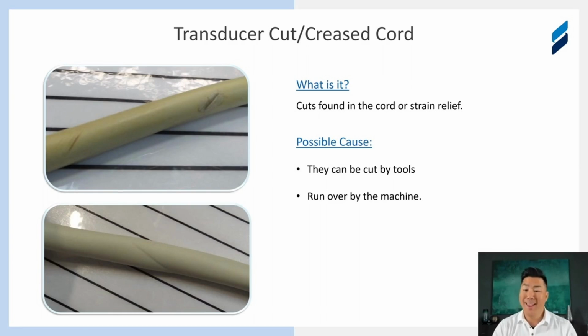noise could be coming from. And it's a great point to train and help educate sonographers to get the cables up off of the ground when you're moving a machine. When you roll them around, the cables do drag on the ground. Those wheels, these ultrasound machines weigh hundreds of pounds, and hundreds of pounds of machine against 42 gauge wires, the 42 gauge wires are going to lose every single time. So something here that could be nothing and could be superficial, but again, we have seen on many occasions that this is the source of a lot of image quality failures by virtue of the lines shorting together or just breaking altogether.